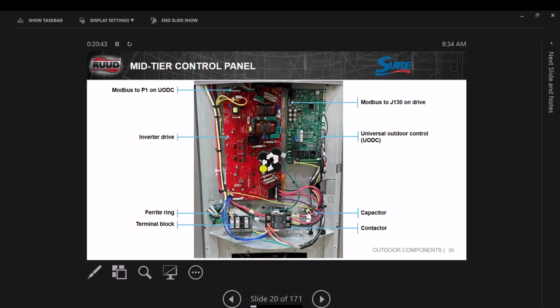When you put the new board in, you're going to put in the serial number of the unit on the app and scan the board, and it's going to load that information from the app into that board for that unit. So it burns the serial number in it. The days that we kept a board on our truck and we put it on there just in case it was bad, and we found out that it wasn't the problem, we pulled it off, put it back on our truck, those are over. Because once you burn that serial number in that board, it's no longer removable out of that unit. Okay, it has that unit serial number married to it. So if you put it somewhere else, it's going to have the wrong serial number, and you can't overwrite that.